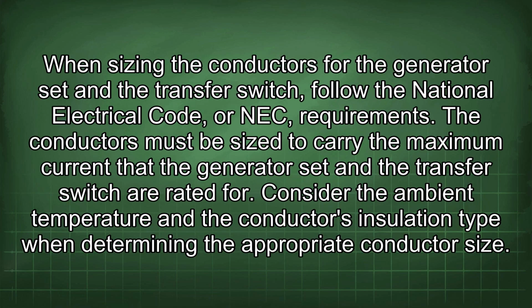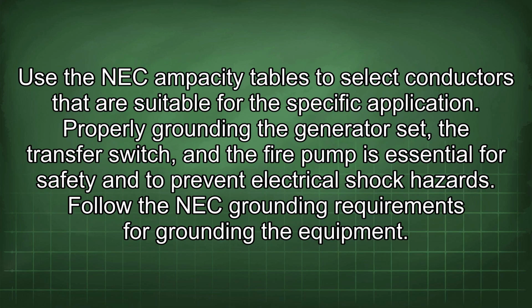When sizing the conductors for the generator set and the transfer switch, follow the National Electrical Code, or NEC requirements. The conductors must be sized to carry the maximum current that the generator set and the transfer switch are rated for. Consider the ambient temperature and the conductor's insulation type when determining the appropriate conductor size. Use the NEC ampacity tables to select conductors that are suitable for the specific application.